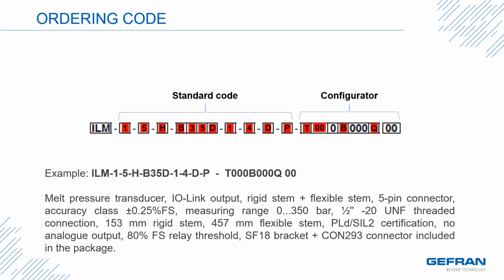We've chosen Performance Level D/SIL2 certification included, no auxiliary analog output, and the safety relay with a full scale alarm threshold set at 80%. Additionally, the mounting bracket and the mating connector are included in the package with this code as shown.